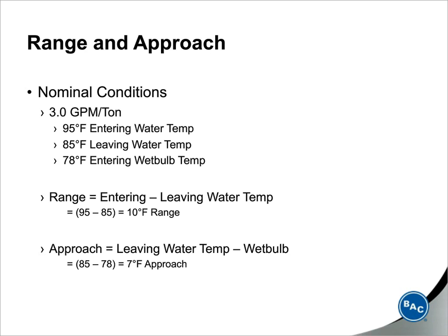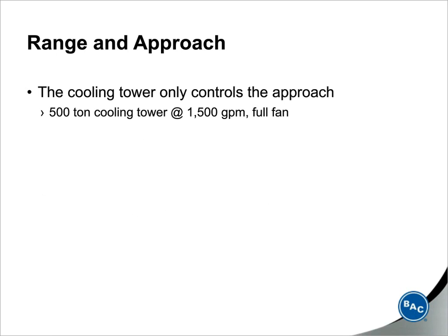I just want to reiterate again, the cooling tower cools to the wet bulb temperature, which is generally lower than the dry bulb temperature, which is what gives evaporative cooling its efficiencies. So the 7-degree approach, again, is the difference between the leaving water temperature and the wet bulb. So the wet bulb is really the temperature that you're trying to cool down to. So earlier I focused on wet bulb temperature, since the design wet bulb temperature is so much lower than the dry bulb. When it comes down to cooling tower and chiller optimization, the approach is absolutely critical.